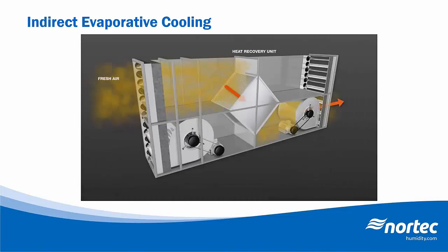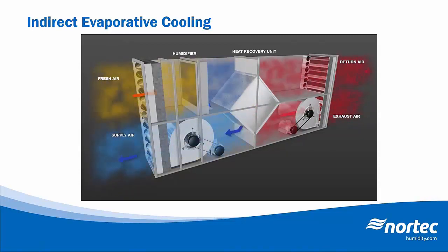The second strategy that we'll look at is indirect evaporative cooling. This strategy uses outside air to cool an internal environment without allowing external and internal air streams to directly mix. In this case, cool outside air is drawn through a heat recovery unit, in this case a plate heat exchanger, then immediately exhausted, while internal air is drawn from the room and circulated through the heat recovery unit before being reintroduced into the room. The outside air cools the internal air through the heat recovery unit without the two air streams directly mixing. Now, by adding an evaporative cooler on the outside airstream prior to it entering the heat recovery unit, the temperature can be reduced and additional cooling can be achieved without adding moisture directly to the supply air.